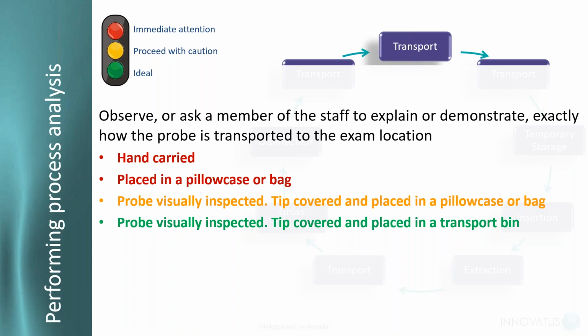Even if the probe is inspected and the tip is covered, it's still in a pillowcase or a bag. The problem with a pillowcase and a bag, for a variety of reasons, is that it's a soft container, and so you have this hard connector, which has sharp edges. It may have pins, maybe pinless, but it has sharp edges, and it can be banging around that bag or that pillowcase up against that fragile tip or the insertion tube. So ideally, we want the probe inspected, the tip covered, and placed in our transport bin.